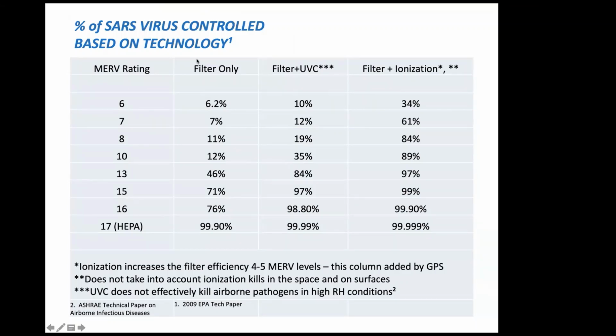And so if you only use filters, a MERV-8 filter, assuming the virus can get back to the filter to be captured, and that's the big assumption here, that filter could stop 11% of it. A MERV-13 filter, 46%. If you combine UV lights with that system, you now can get 19%. A MERV-13 jumps you to 84.